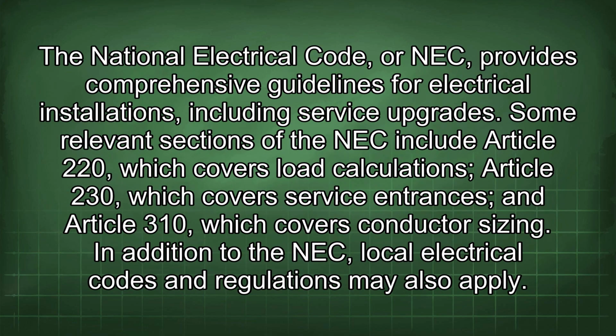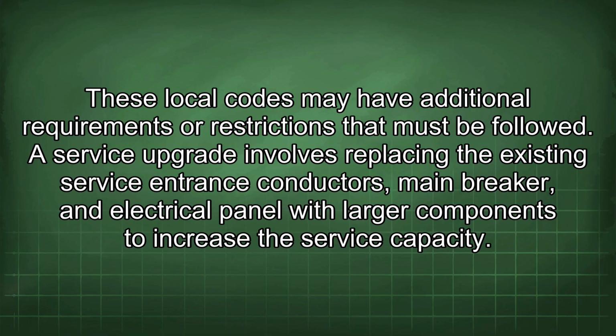The National Electrical Code, or NEC, provides comprehensive guidelines for electrical installations, including service upgrades. Some relevant sections of the NEC include Article 220, which covers load calculations, Article 230, which covers service entrances, and Article 310, which covers conductor sizing. In addition to the NEC, local electrical codes and regulations may also apply. These local codes may have additional requirements or restrictions that must be followed.